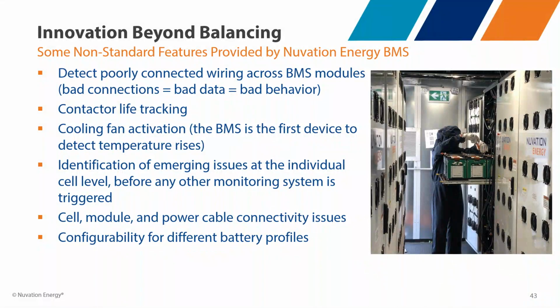This has a number of key advantages. One main advantage is if you're augmenting a system, say 10 years later, you don't have to use the same battery manufacturer or even the same chemistry. Especially with a string inverter system, the Nuvation BMS can install a different battery manufacturer or chemistry into the existing energy storage system and still present the same hardware and software interface to higher level controllers. Effectively, our BMS acts like a device driver to abstract the battery and chemistry underneath. That's one of the key advantages there.